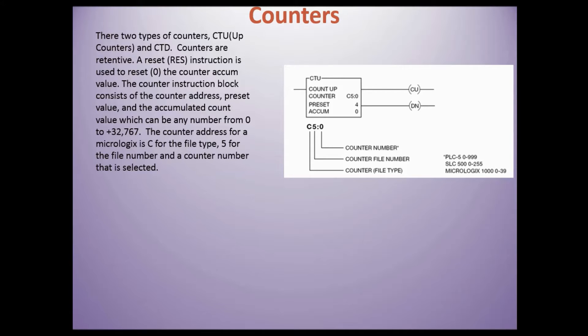And you have your cumulative count which can be any number from zero to 32,767. The counter address for a MicroLogix is C for the file type, 5 for the file number, and a counter number that is selected.